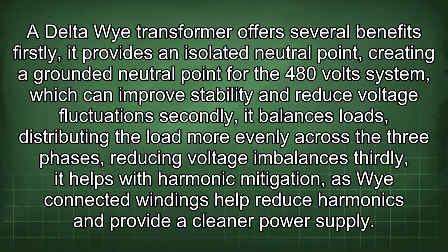Firstly, it provides an isolated neutral point, creating a grounded neutral point for the 480-volt system, which can improve stability and reduce voltage fluctuations. Secondly, it balances loads, distributing the load more evenly across the three phases, reducing voltage imbalances. Thirdly, it helps with harmonic mitigation, as Y-connected windings help reduce harmonics and provide a cleaner power supply.